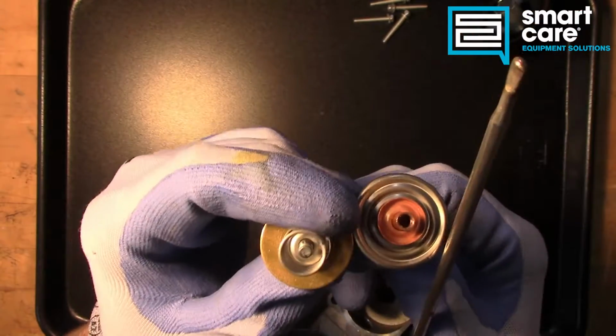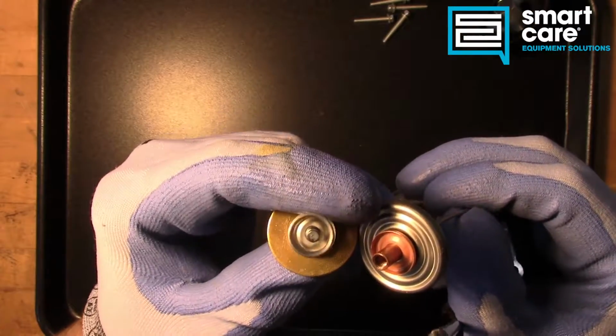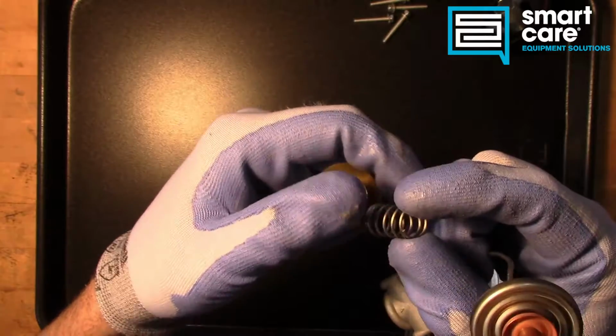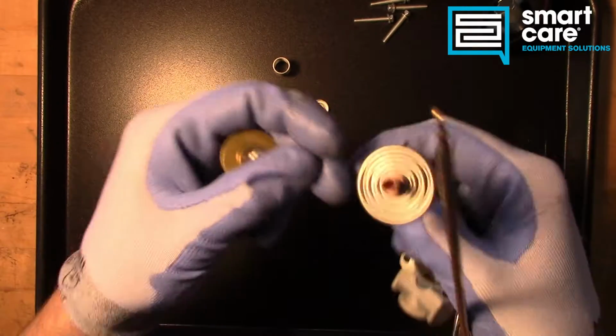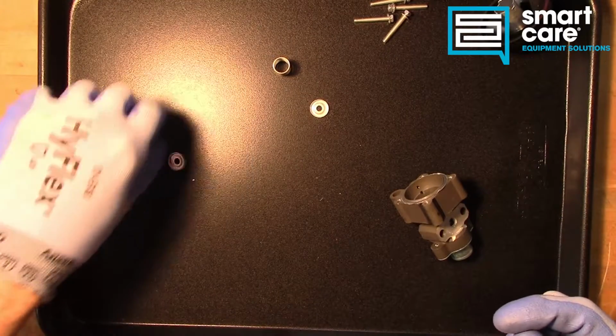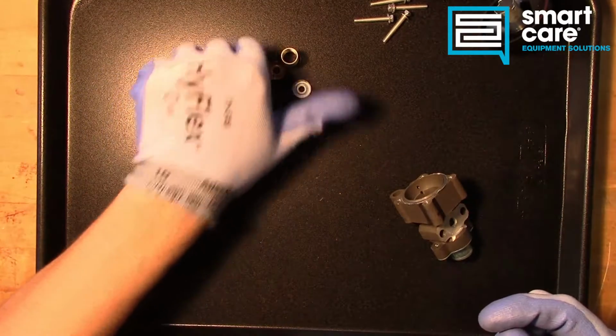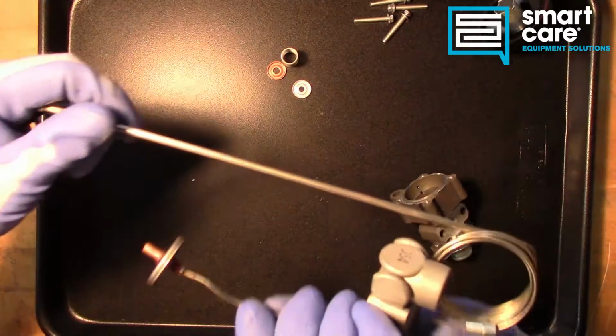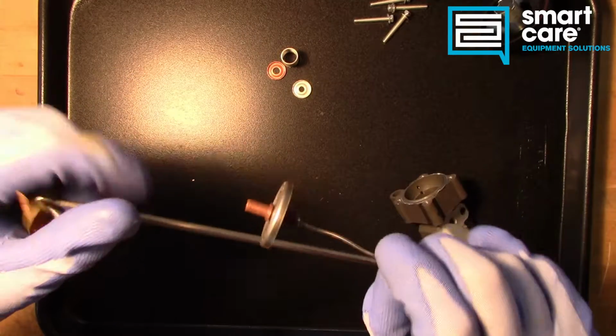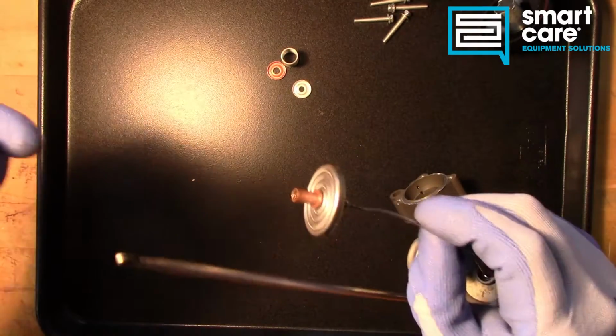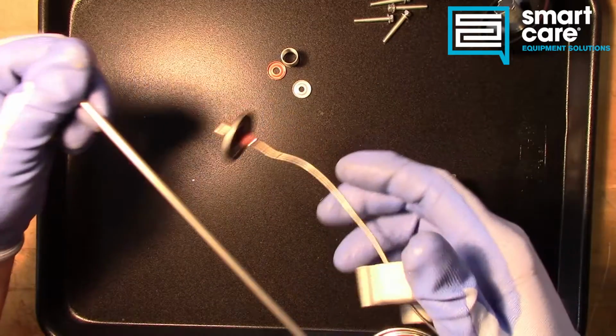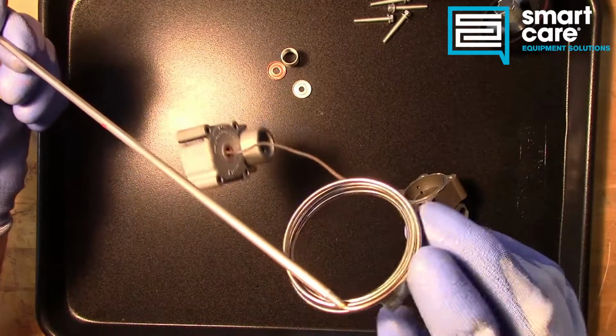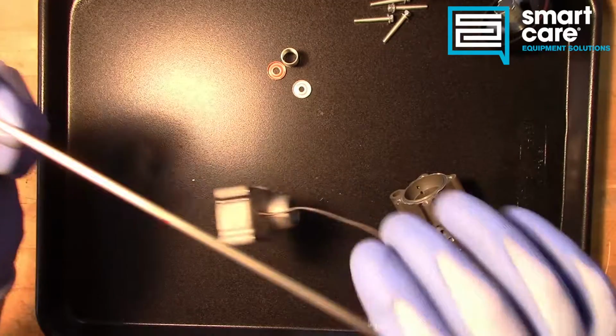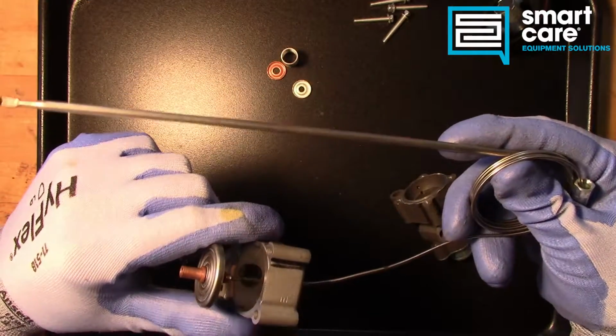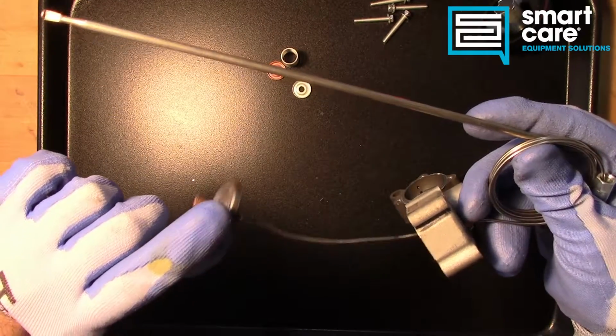So there we've just turned it all the way apart. It looks like it's actually reverse threaded. So here's our spring. And then there's just a little spacer washer there. Set those off the side. And then this is our bellows and cap tube and bulb. So this is the part that's really easy to damage during installation. If this becomes kinked or crushed, this thermostat will not function correctly because you'll have changed the amount of pressure on this bellows.